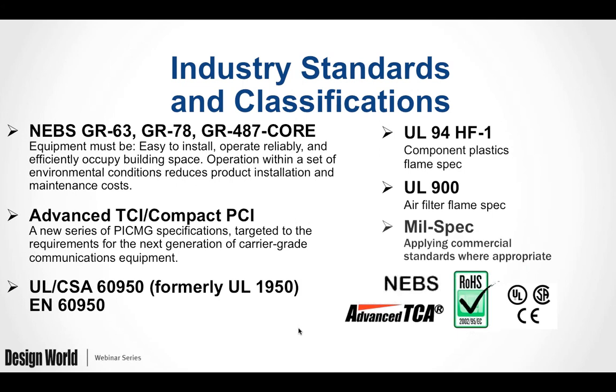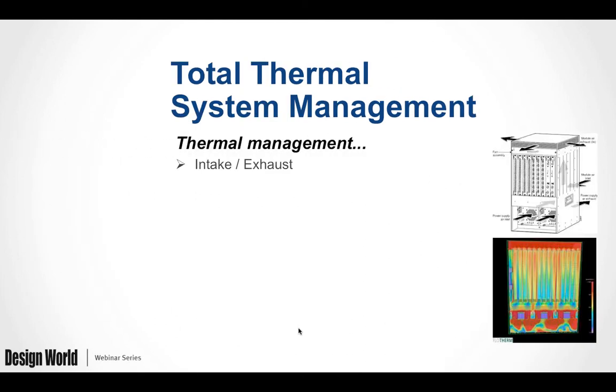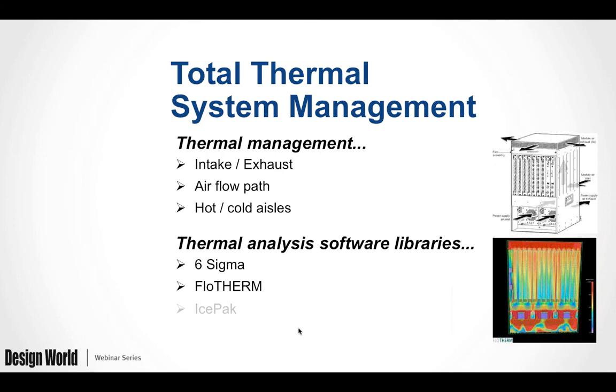It's important to be aware that customers require compliance with telco and data center industry-specific standards such as NEBS and ATCA, as well as general enclosure ratings like UL 60950. Compliance with these standards indicates adherence to the gold standard when it comes to equipment reliability, safety, and interoperability. UL 94 and UL 900 are component plastics and air filter-specific flame ratings, and they are sub-requirements referenced within the NEBS and ATCA standards. There are also thermal management design considerations used to dissipate harmful heat buildup in densely populated chassis.